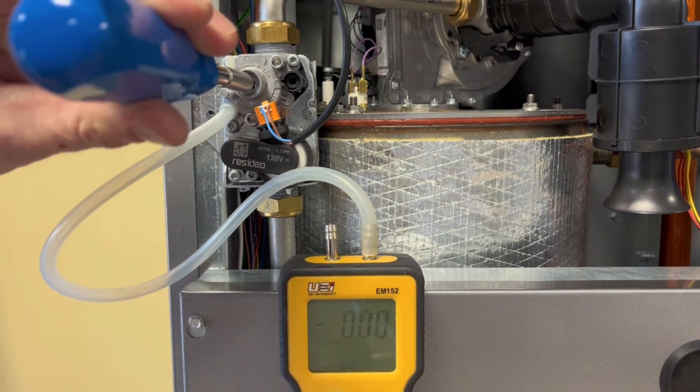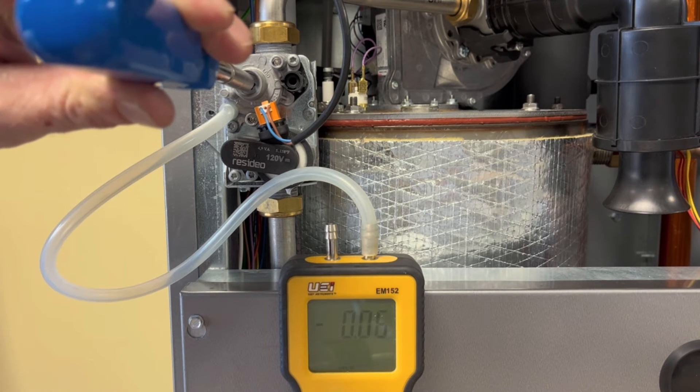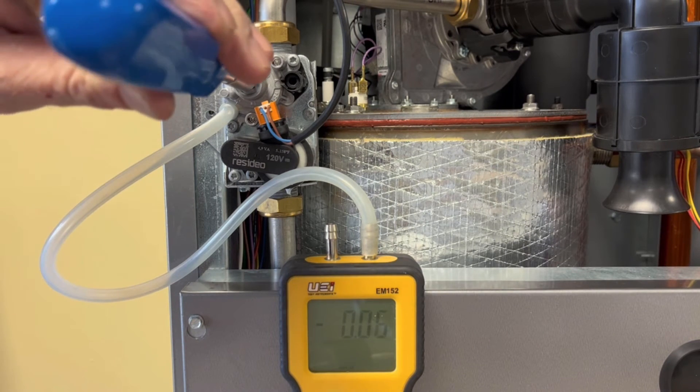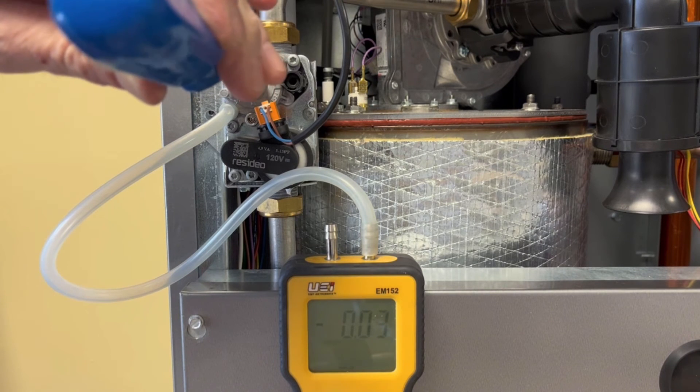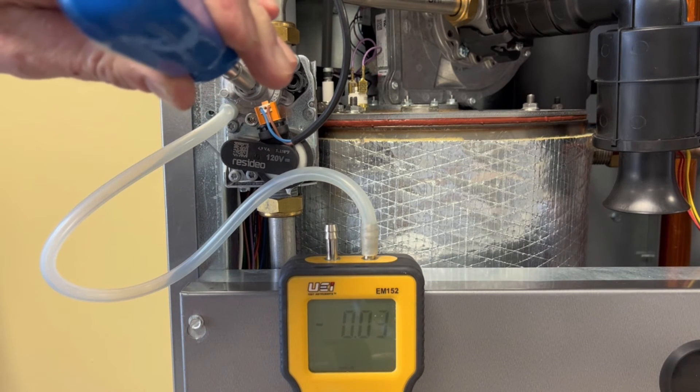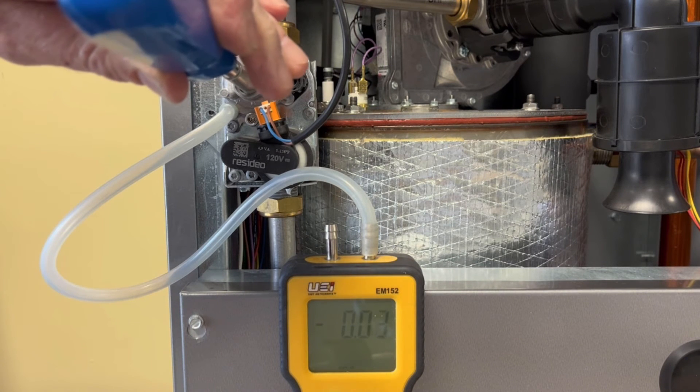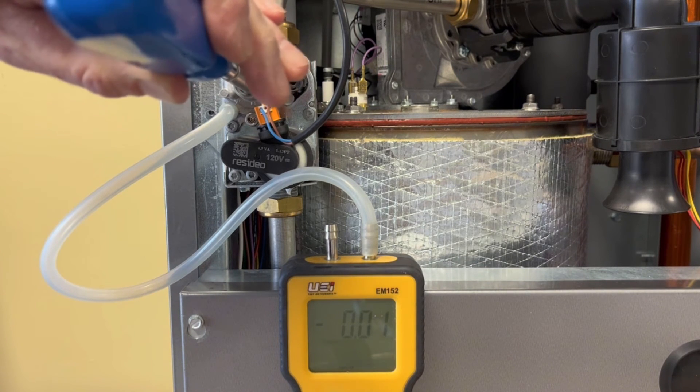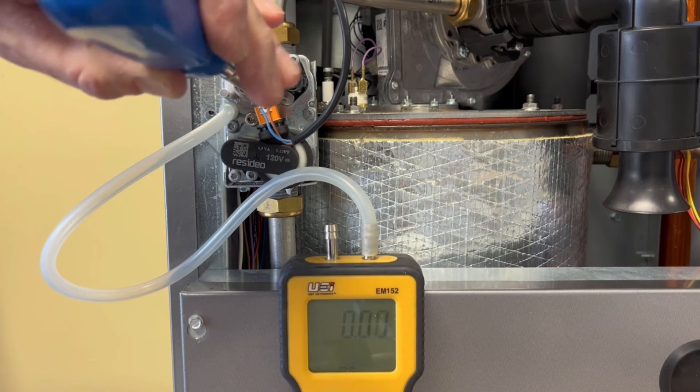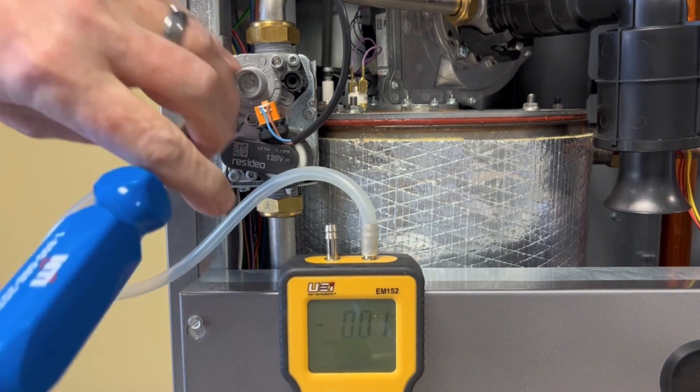Ensure you zero your manometer before beginning this procedure. Carefully and slowly adjust the screw until you see approximately zero inches water column on your manometer. At that point, you can now complete a low fire combustion analysis. Use the specifications in the installation manual to set the CO2 to the correct setting.